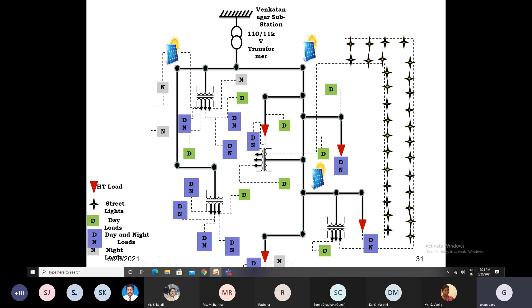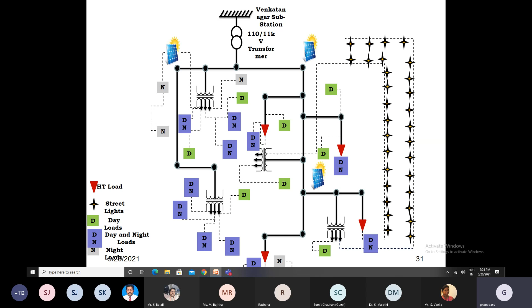So in order to avoid that, the better way of placing the solar is to compute our diurnal load factor and place the solar accordingly. Also, if the solar penetration is greater than 30%, we have to go with a smart inverter which is capable of producing pseudo inertia as well.